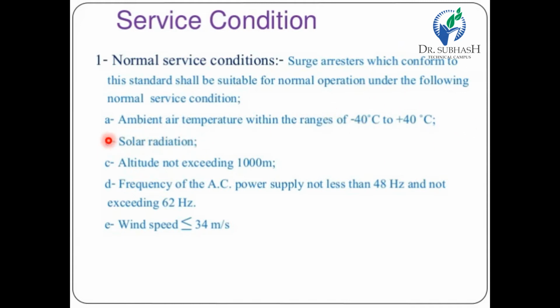Another one is solar radiation, then altitude not exceeding 1000 meter, frequency of AC power supply not less than 48 Hz and not exceeding 62 Hz. Wind speed should be less than or equal to 34 meter per second. So these are the conditions. If all these conditions are satisfied, then we can say this is the normal service conditions.